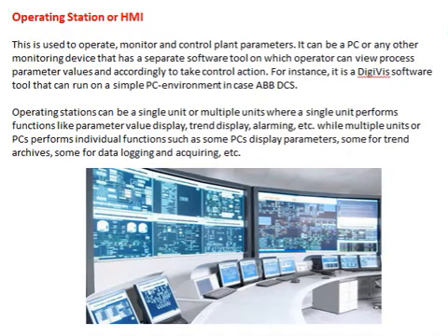Operating station or HMI. This is used to operate, monitor and control plant parameters. It can be a PC or any other monitoring device that has a separate software tool on which the operator can view process parameter values and accordingly take control action. For instance, it is a DCS software tool that can run in a simple PC environment. Operating stations can be a single unit or multiple units, where a single unit performs functions like parameter value display, trend display, alarming, etc. While with multiple units or PCs, individual PCs perform individual functions, such as some PCs displaying parameters, some for trend archives, some for data logging and acquiring, etc.